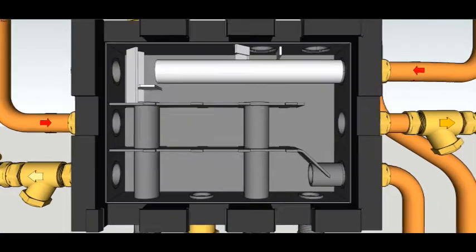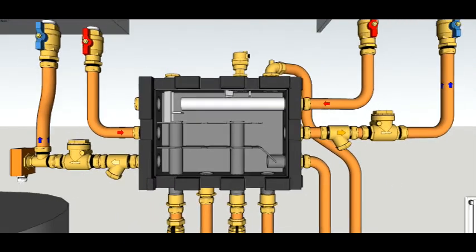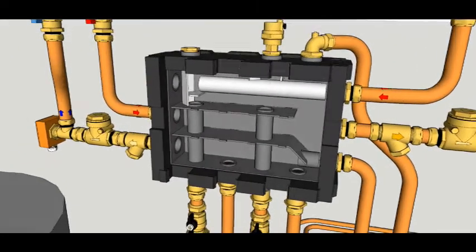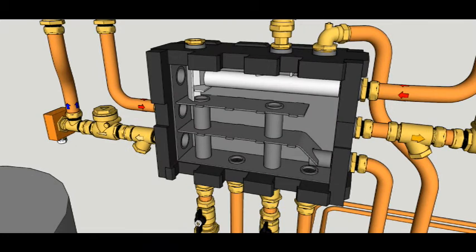We've now removed the front insulation and the front plate of the energy zone, and inside you can see the baffles and the internal pipework. There's two long vertical pipes rising up into the top chamber. They would be used to draw the water down onto the respective pumps for the zones. The returns for those zones are to their right hand side and they arrive into the bottom chamber or return chamber. The middle chamber is a bypass chamber and there are many uses for that.